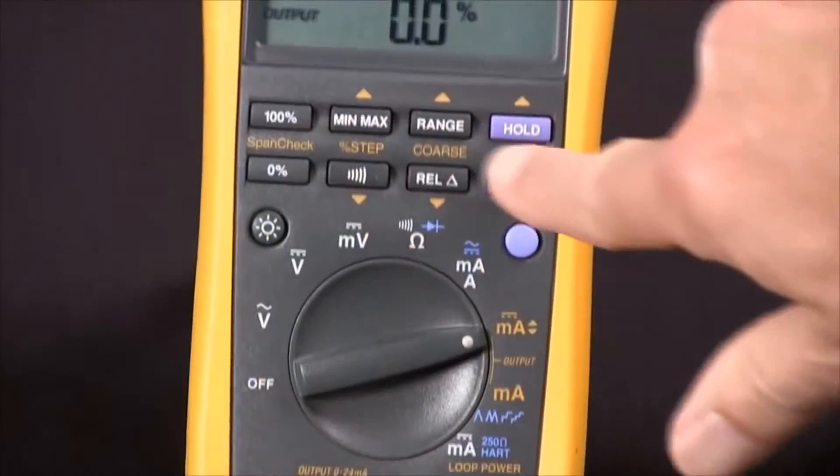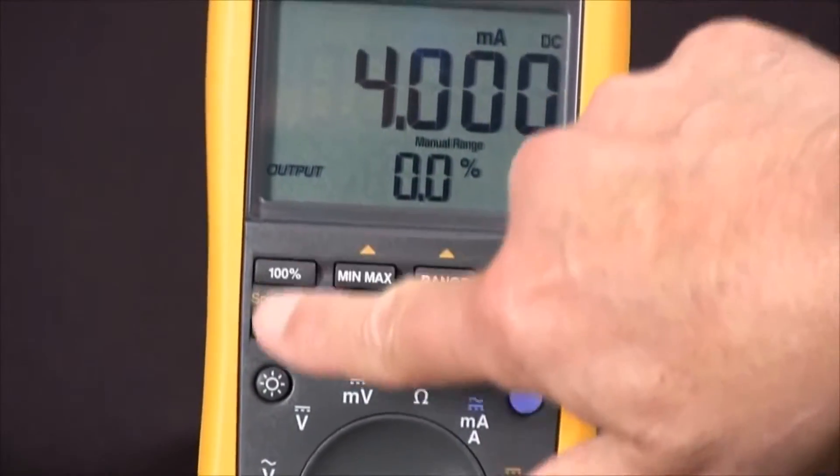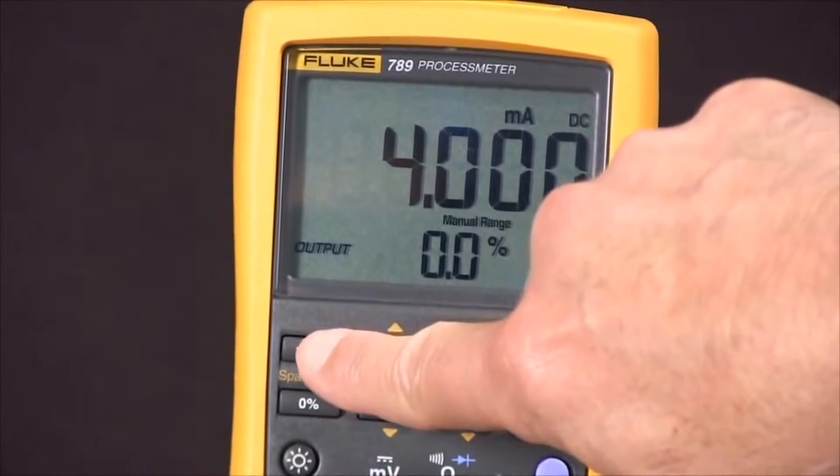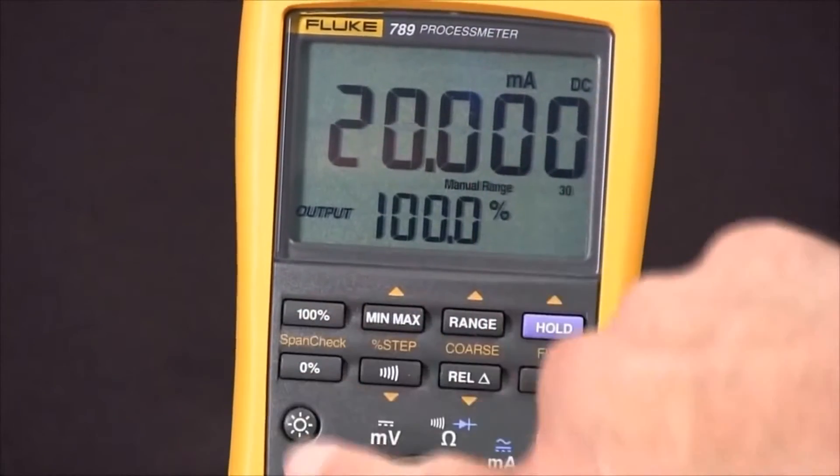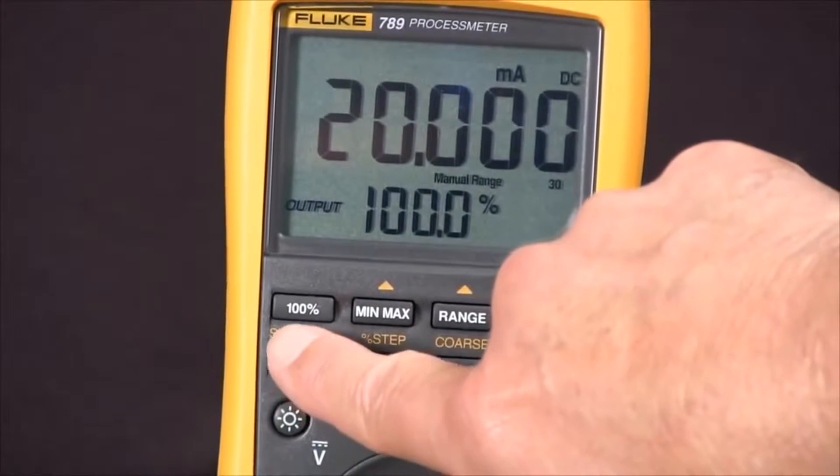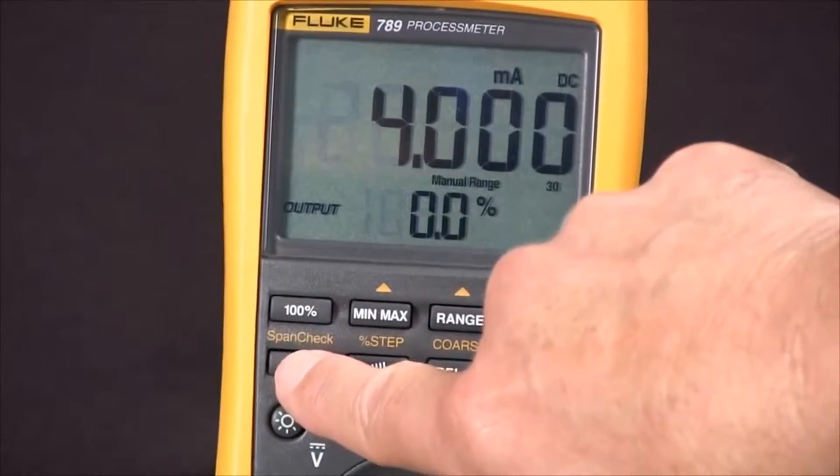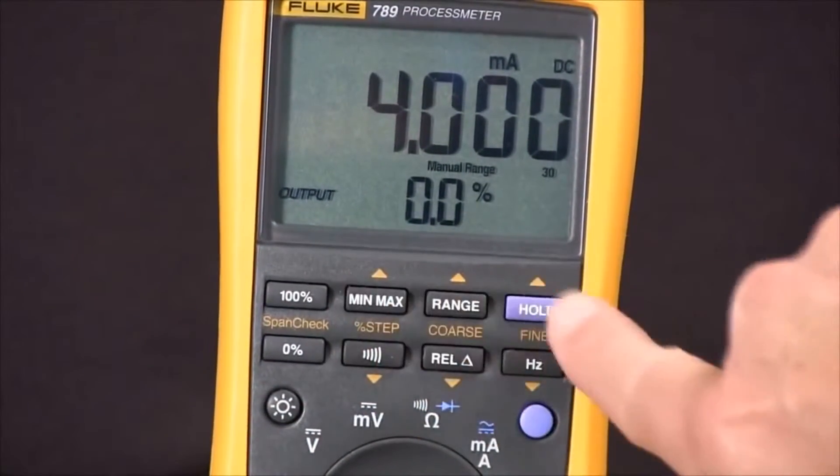We can start over here with the span check and we can go from zero percent of span to 20 milliamps or 100 percent of span or zero. And then with these three we can do percent step, coarse or fine adjustments.